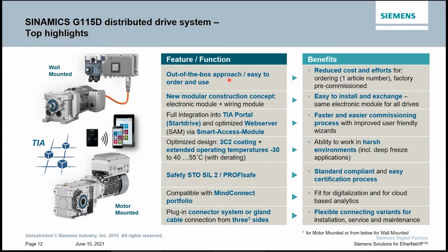So you order a 5 horsepower G115D, it is compatible with a 5 horsepower motor. So from an integration standpoint, startup standpoint, it saves money. Everything's pre-commissioned, saves time and money. There's a modular construction concept. You have the electronic module and the wiring module. That makes it for ease of installation, ease of troubleshooting, ease of maintenance.